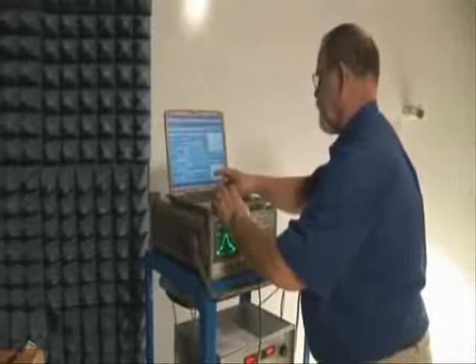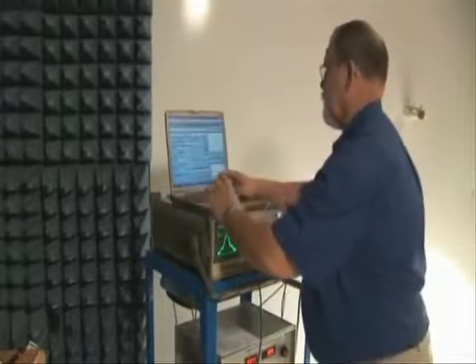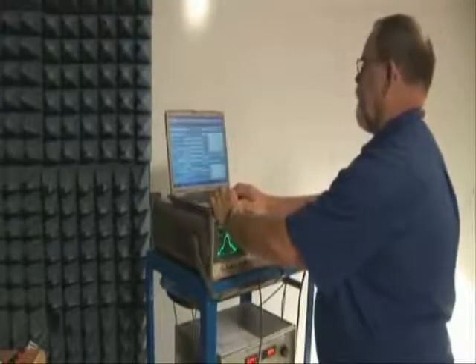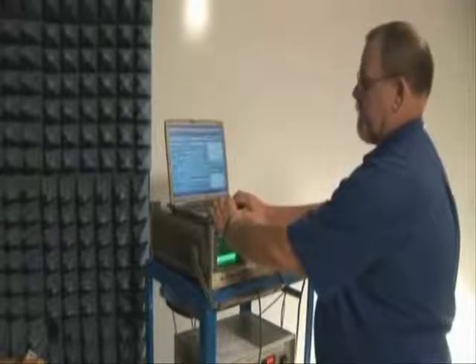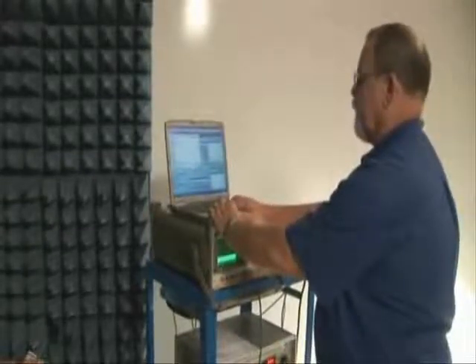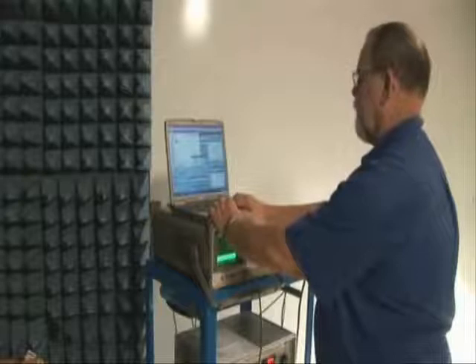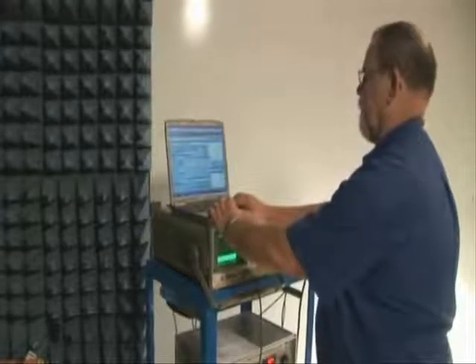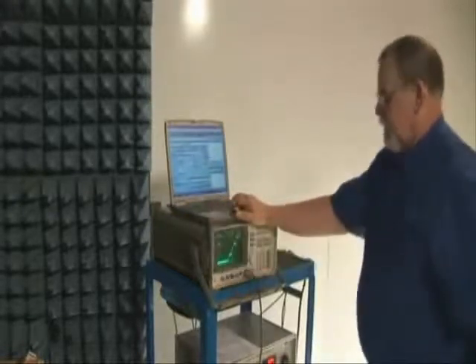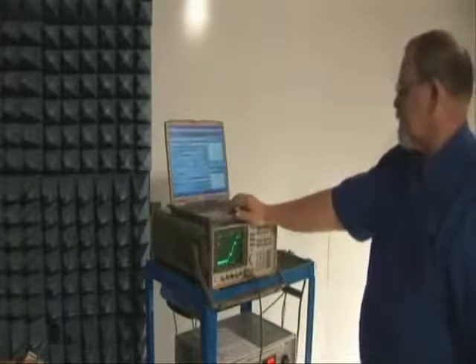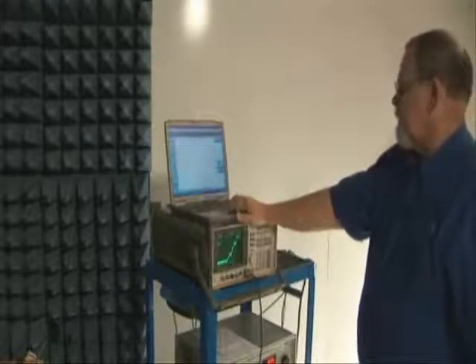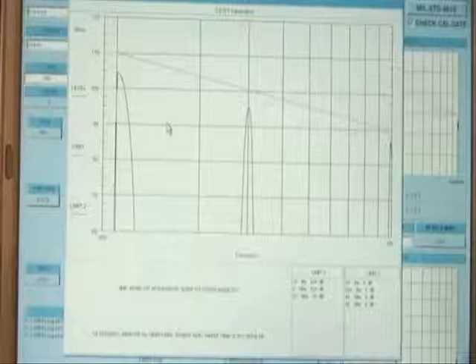9 kilohertz to 10 kilohertz for our frequency span. Run the software, the same hardware is in play. We overwrite the file one more time. Yep. And we should collect a piece of data that shows that this measurement should be approximately 6 dB below the limit, and it's in fact about 4.5.